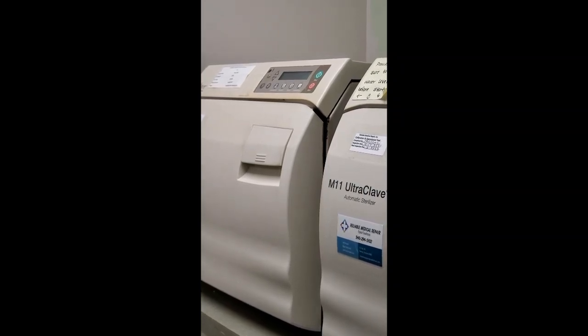So this does just take a few minutes so the pressure can come down enough so it's safe for the door to pop open slightly. So this machine automatically vents. There are other machines where you have to do the venting for it. So for those machines, you would have to turn it to the vent setting and then ever so slightly just open that door so that way the steam could come out. But like I said, this one's automatic, so we don't do anything. It's going to vent on its own.